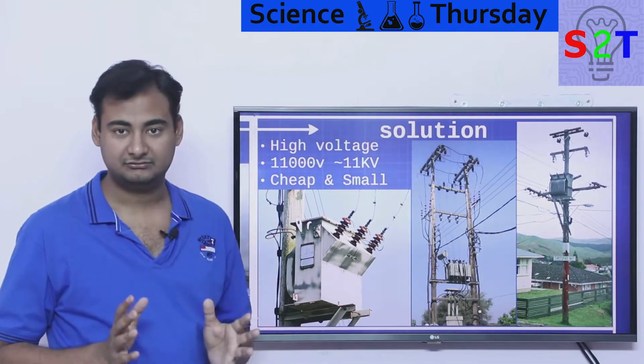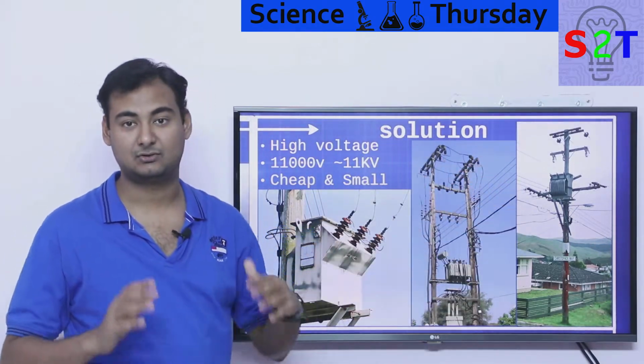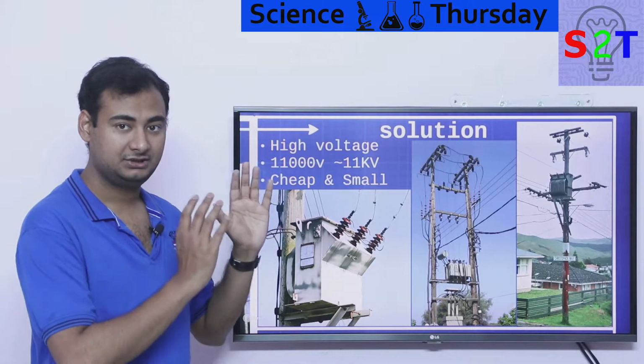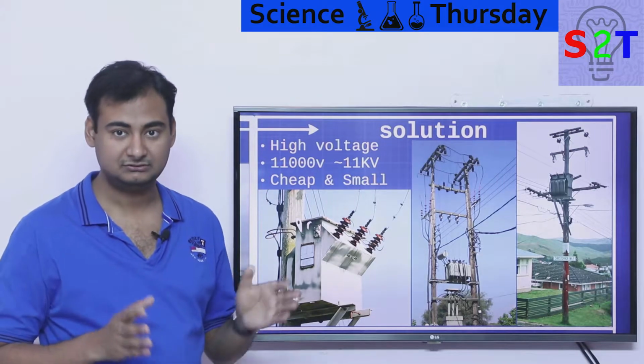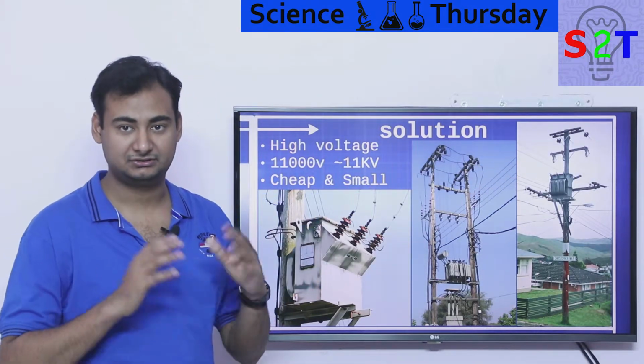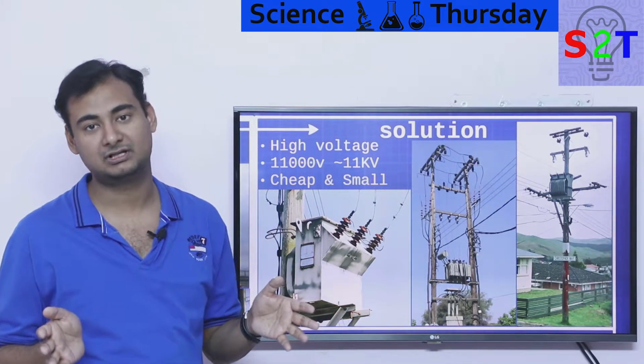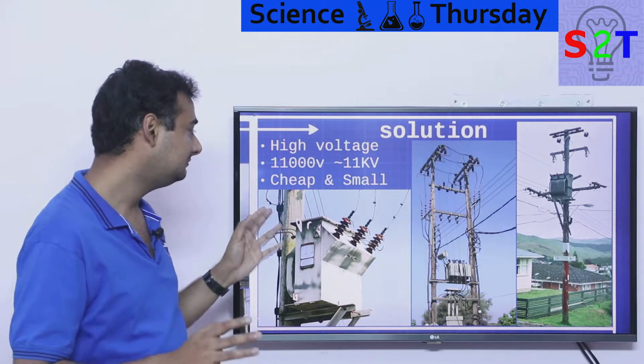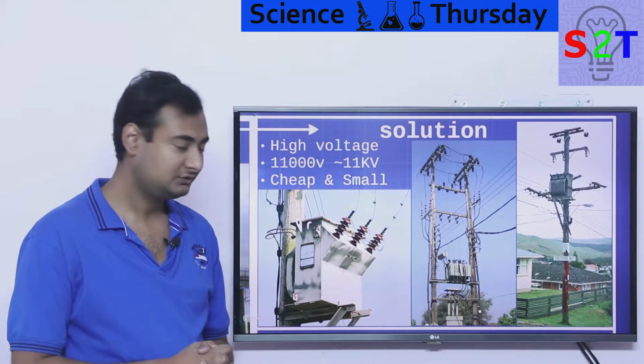So this is why we built this miniature substation that is on a pole. That's the idea. You reduce the voltage as much as you can to make sure the air can handle it, your exposed conductor can handle it, and your pole does not become ludicrously expensive. And then we created small, cheap transformers to run on it.